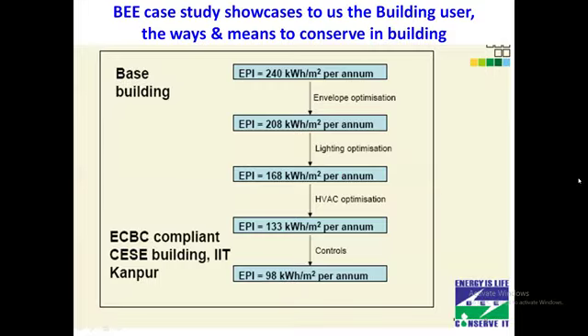It needs to be diffused inside the premises. That is what we are concentrating more now. Then the HVAC optimization. This is where previous HVAC, all this 100 tonner or 200 tonner or 500 tonner, were all operating almost around 1.5 to 2 kilowatt per ton. But thanks to a lot of innovations happening in the HVAC, it is coming down to 1 kilowatt per ton, and somewhere it is around 0.75 kilowatt per ton, and the major green buildings are all aiming for almost 0.5 kilowatt per ton.